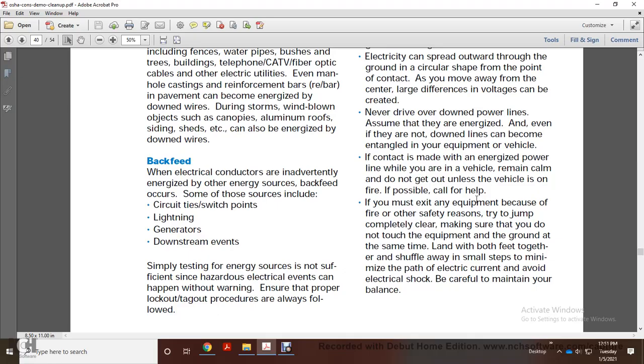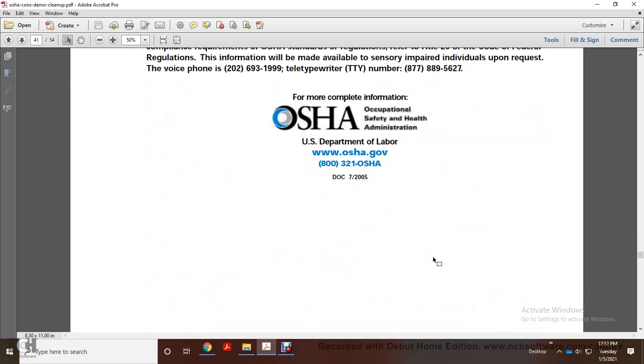If you must exit the equipment because of fire or other safety reasons, try to jump completely clear, making sure that you do not touch the equipment and the ground at the same time. Land with both feet together and shuffle away in small steps to minimize the path of electrical current and avoid electrical shock. Be careful to maintain your balance.